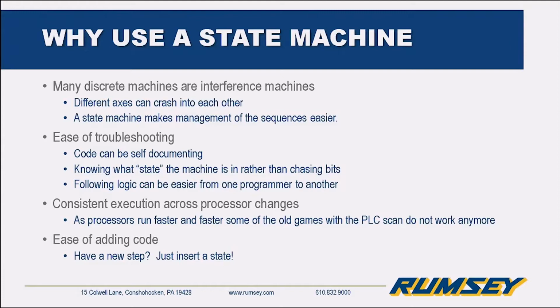Another thing that a lot of people have run into, and I personally, Sean as well, is that as processors get faster and faster, or with the big leap from, we'll say, PLC-5s and SLCs, a traditional PLC, to Logix 5000, some old tricks with the way a PLC would scan through its code, then update outputs, so on and so forth, don't necessarily apply. Specifically, in Logix 5000, the I/O is updated asynchronously to the program scan at some RPI or some rate. So some of those little tricks to manipulate the PLC scan don't necessarily work. A state machine can help with that by keeping it in an orderly fashion.